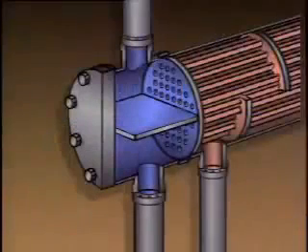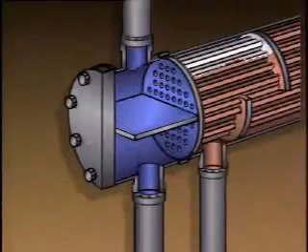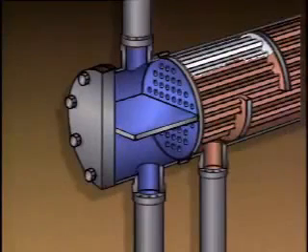When air, non-condensable gases, or other vapors are trapped inside a heat exchanger, they can prevent the unit from operating efficiently. This is because the air or gas can either blanket the tubes or block the tubes off and prevent fluid from flowing through them. The effect is the same as the effect created by fouling — less heat can be transferred across the tubes. Gas trapped on the tube side can block off tubes and prevent fluid from passing through them. Gas trapped on the shell side can displace the shell side fluid at the top of the heat exchanger, reducing the amount of tube surface area exposed to the shell side fluid, and thus reduce the amount of heat that can be transferred.